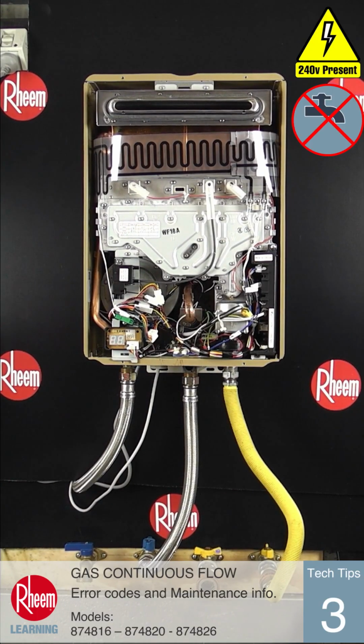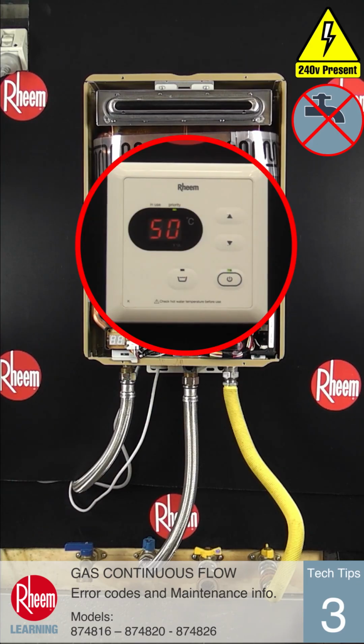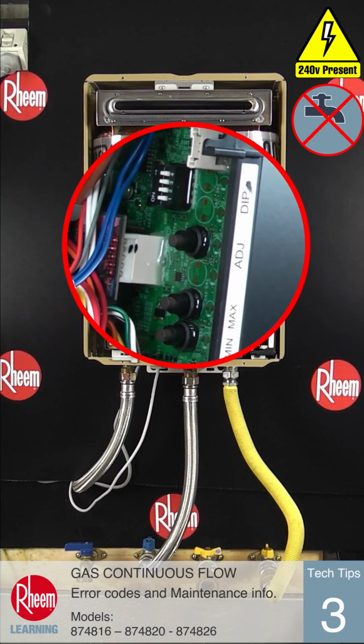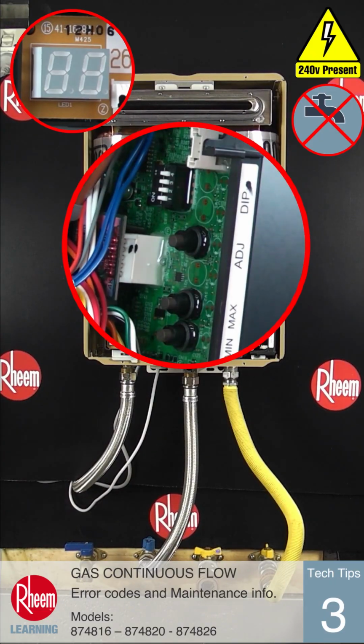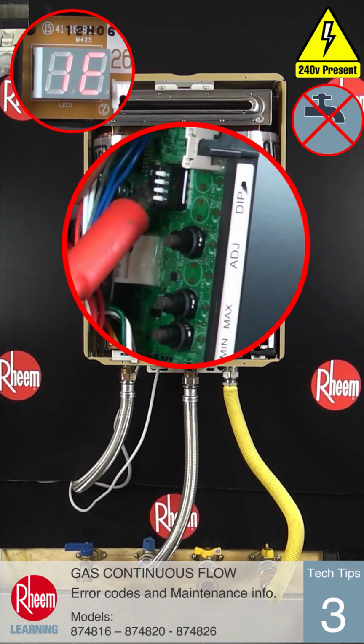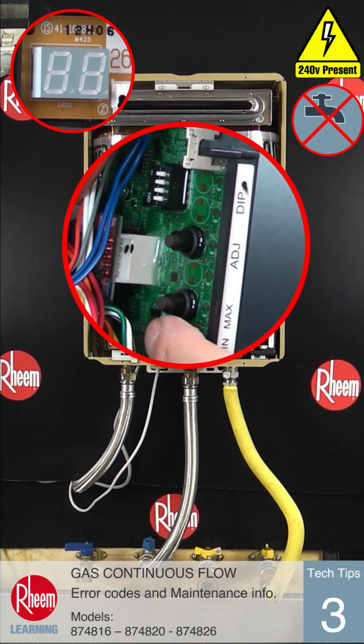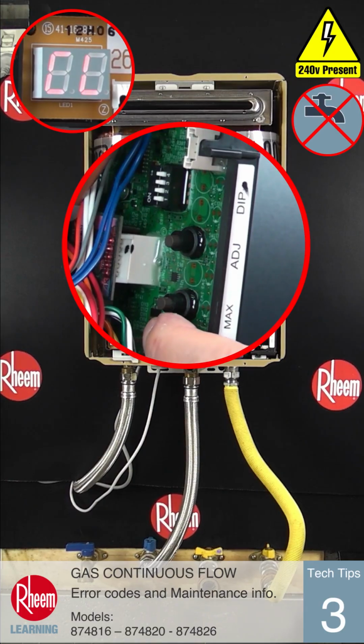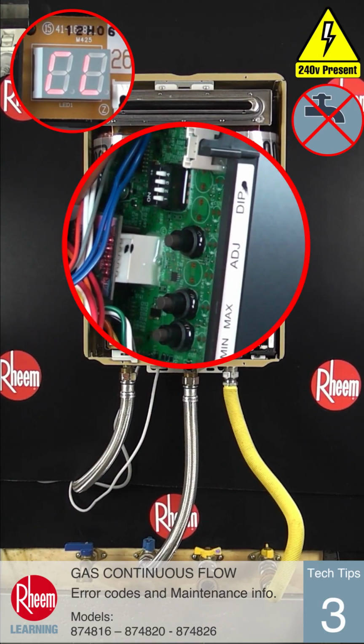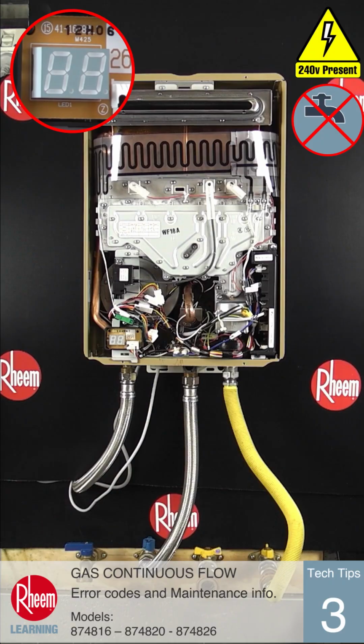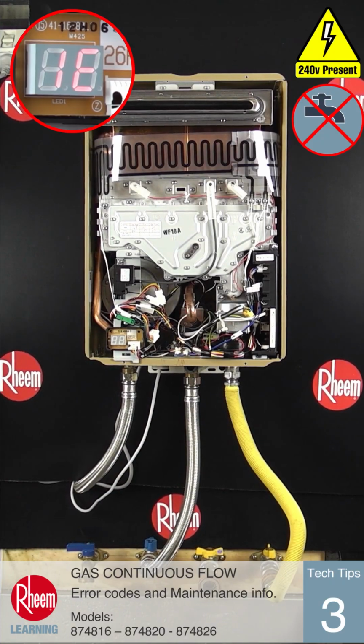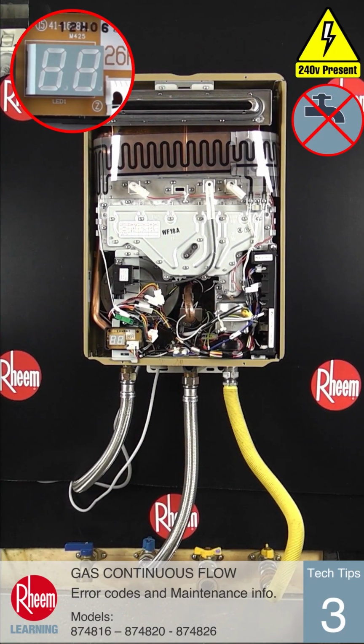To do this, any wired controllers on the system need to be turned off. Then turn dip switch number 1 on and then off again. Within 5 seconds, press and hold either the max or min button until CL is shown on the LED display, indicating the history has been cleared. Each error memory location will now display 2 dashes to indicate they're empty.